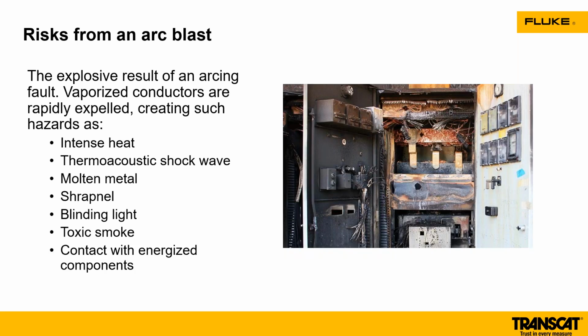Once we have an arc flash, typically the arc blast comes next, depending on the energy that's involved. With that, you can literally have intense heat. There could be a shock wave, depending on how much energy is there. Molten metal, shrapnel, that blinding light. If you go out and look at arc blast videos on YouTube, it's a tremendous amount. It's incredible. A lot of the people that are involved, unfortunately, are fatally harmed, or there's severe damage to their bodies based on that arc blast.